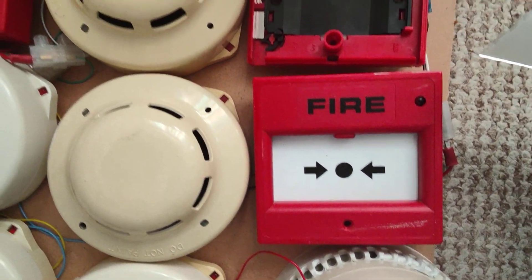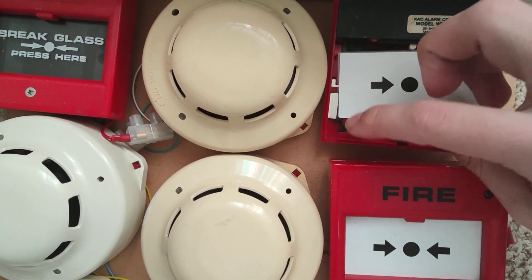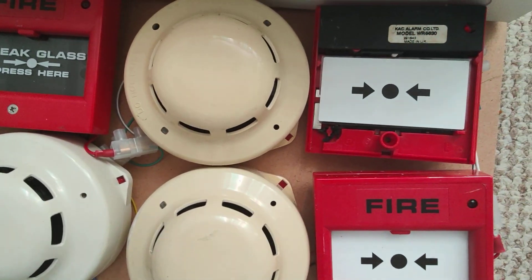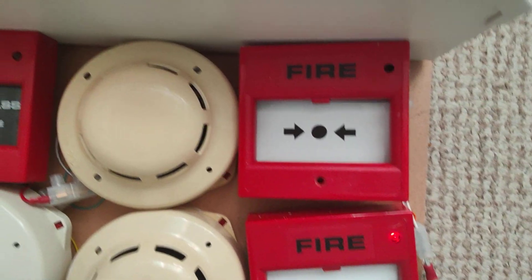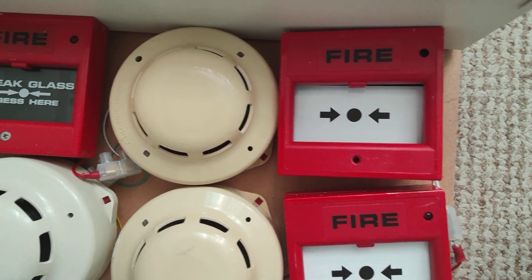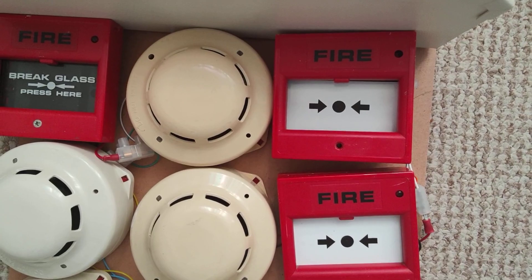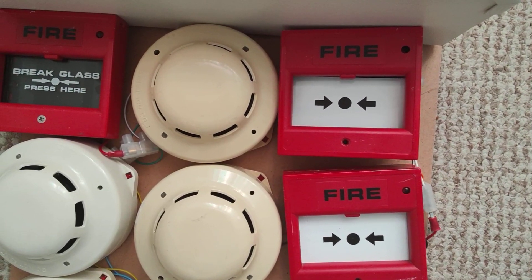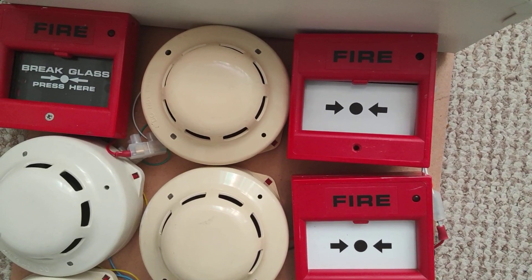Now it's stopped. It's polling really fast now because it wants to check more frequently to make sure it's not still in alarm — which it's not — so I can reset it. It stops polling for a bit, and then it'll start doing it again at normal speed.